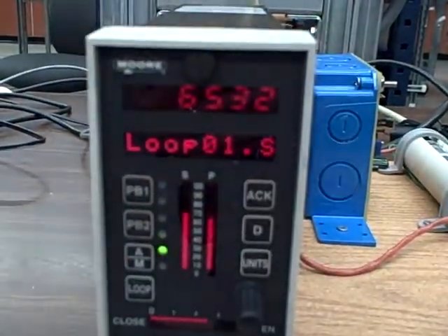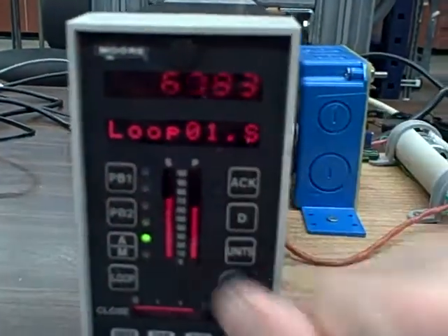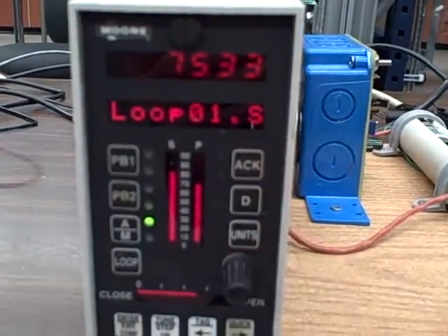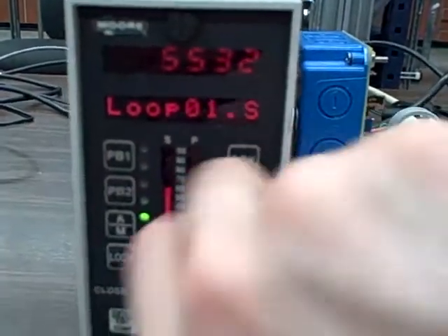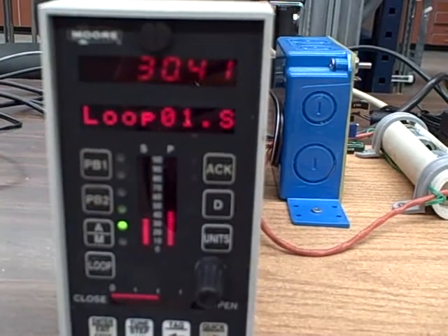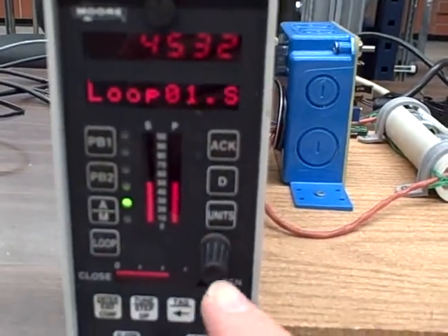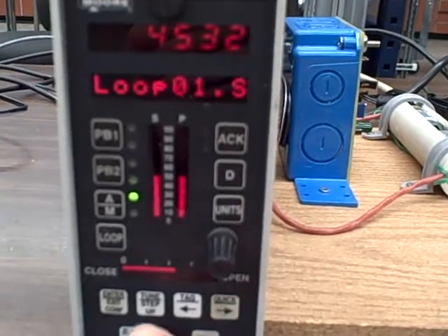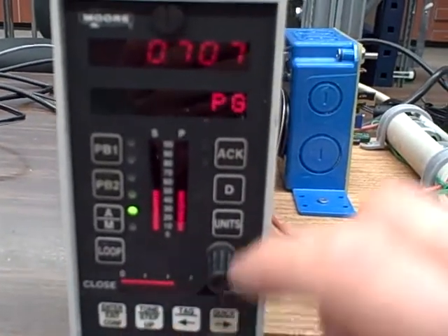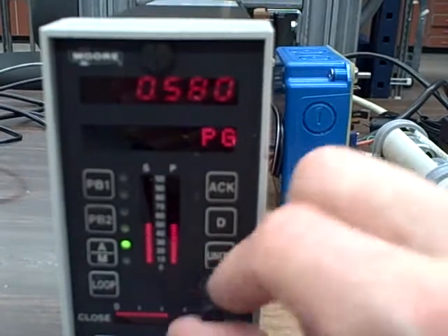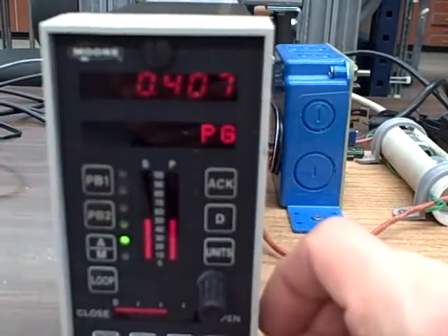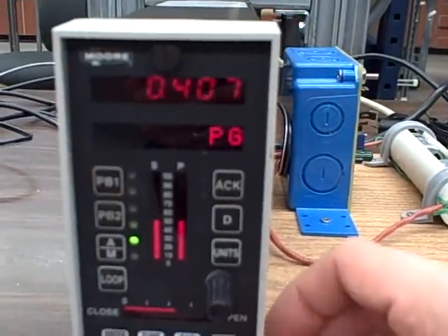And you'll notice when I adjust set point, there's a little bit of oscillation in the process variable, not nearly as much as what we had before. There still is some, though, and so if I were dissatisfied with that level of oscillation, I can decrease the gain even more. Let's do that. I'll bring the gain down to about 0.4, and I'll store that value.